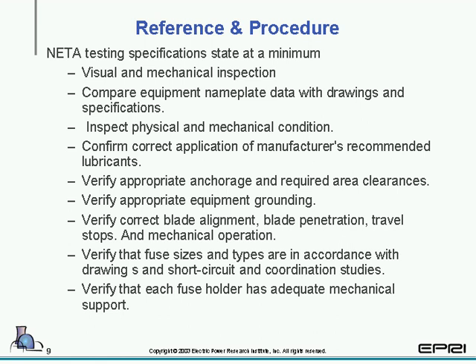Yeah, I think blade should be breaker, right? Breaker alignment and breaker penetration, correct? Well, actually, we have breaker alignment. Blade penetration is a different design. Some breakers actually have where the breakers come up and touch flat. Others are a wedge design or a knife design, so they slide in between the contacts, even on the moving. Okay, so you're talking contacts. Okay, that is correct. Okay.